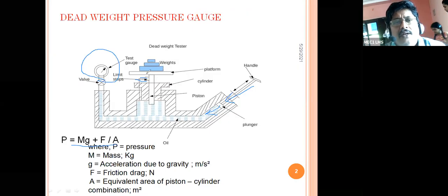So here, the test gauge that we have to test is incorporated, and this is a valve. A platform is there, and weights are added similarly. The piston drops down, and we have to push the plunger with the help of the handle, so pressure is created inside. Same as before, the piston moves up and floats between the two limit stops.